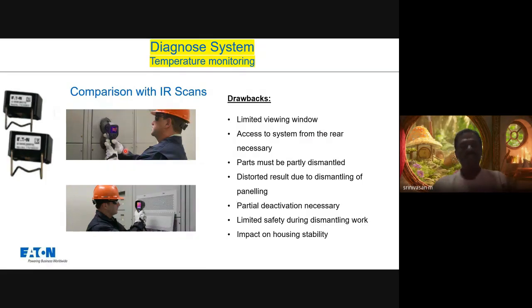So normally what will happen is, after energization of the switchboard, once in a year or once in 2 years, the FM team will use a thermal camera and measure the temperature of the joints. There are some pros and cons, but mainly we could see there are a lot of drawbacks. For example, if you look at this picture, this FM team person is trying to take the temperature on a particular phase of the bus bar. You know very well, exactly behind this door, maybe you will see only one particular phase, maybe red or yellow or blue only. You cannot measure the temperature of all the three phases within this small window. It is difficult to do that.